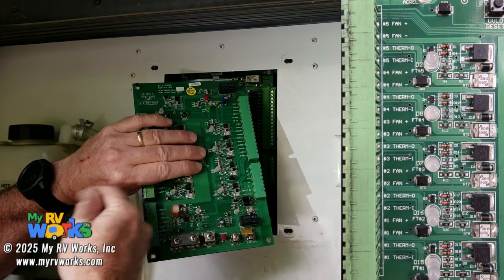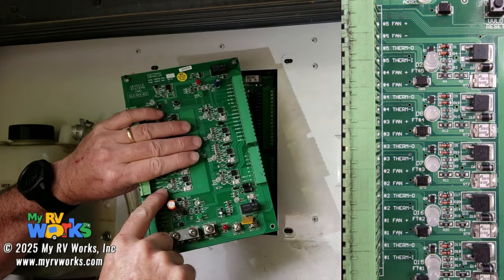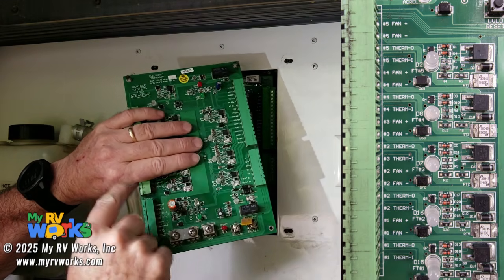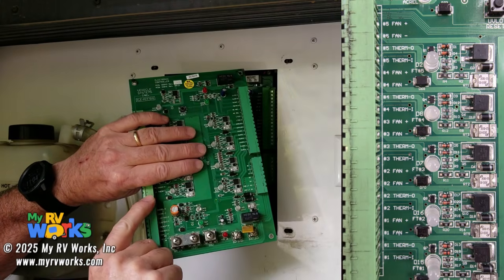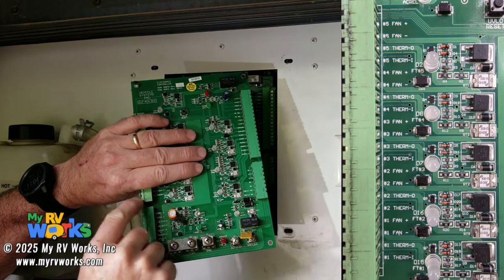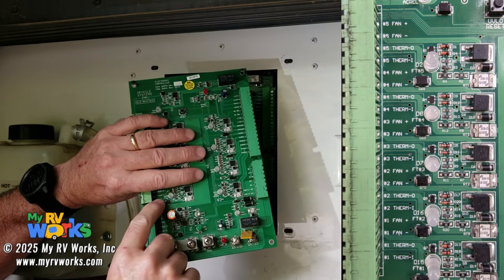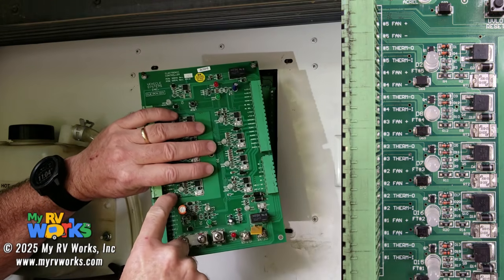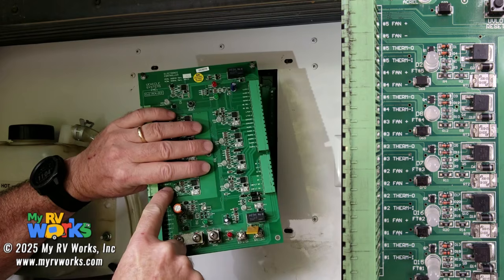So basically I've got 12 volts leaving, and as soon as I get 12 volts coming back in on my thermostat I, that tells the board, hey, we got a call for heat in zone 1, 2, 3, 4, 5. So that's wonderful. That just solved the riddle of this thermostat I, thermostat O, didn't it?